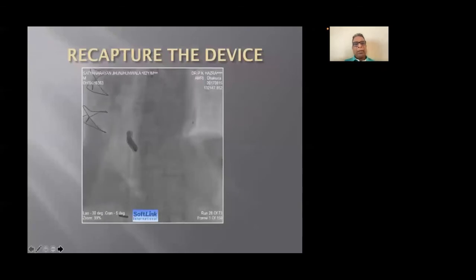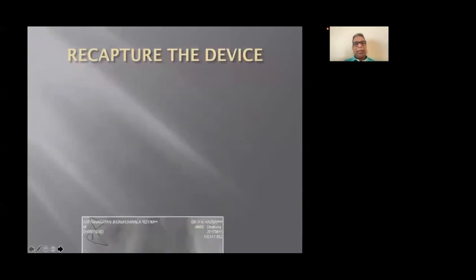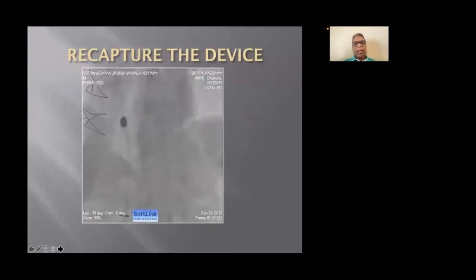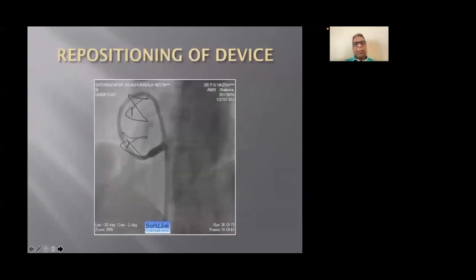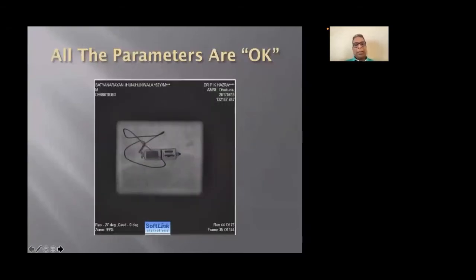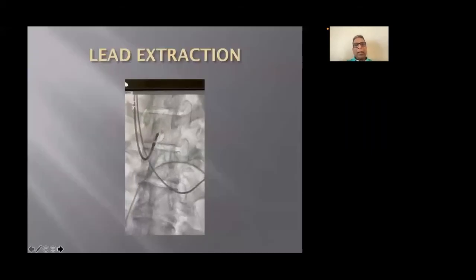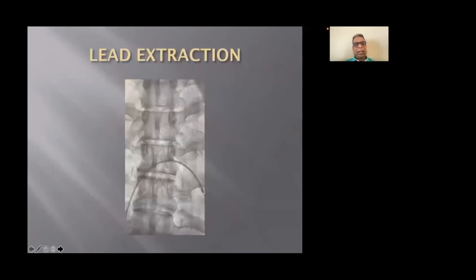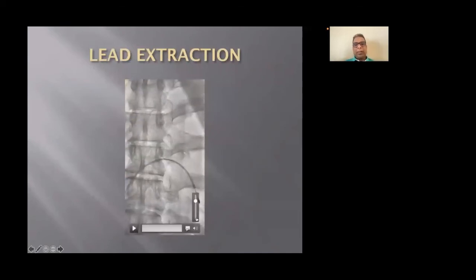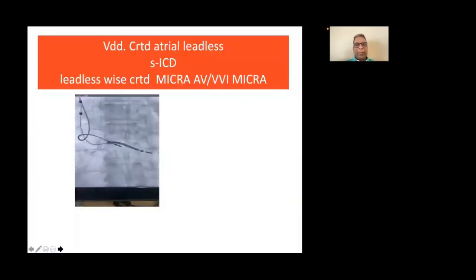It is better to check in 2 views for the recapturing and the alignment of the device. If you do not have this alignment, your Micra can get damaged. So it is better to come back to the RA, pull back the whole device and reload it. As I said, post CABG or no CABG, but if you have a transplanted heart, it is a little bit difficult. For a permanent pacemaker in a transplanted heart, I have only one experience. This is around 5 to 10% post-TAVR, and if you have an infected lead, you can extract the lead, then you can go for this kind of implantation. You can wait for 24 hours, but most of the time it is very, very effective.